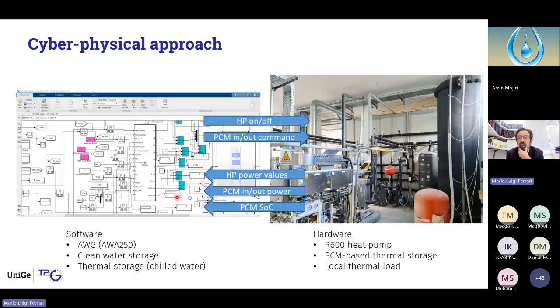In real-time mode, there is an input-output interface to be able to perform tests in a so-called cyber-physical mode. So the optimizer calculates the on-off signal for the heat pump and the in-out command, so charging or discharging, for the phase changing material tank. If it is in charging or discharging phase, it also gives a command of kilowatt power to be exchanged. These data are the set points calculated by the model, so the signals from the optimizer output, transferred to the test rig for managing the plant.